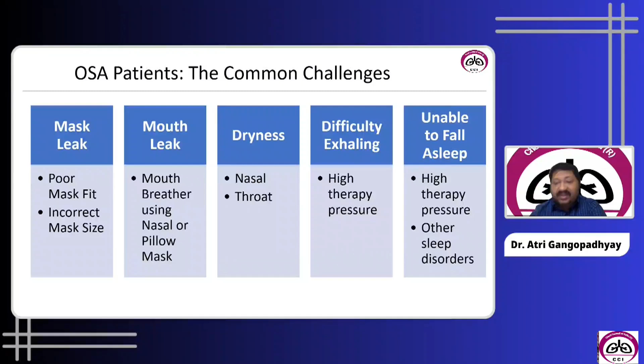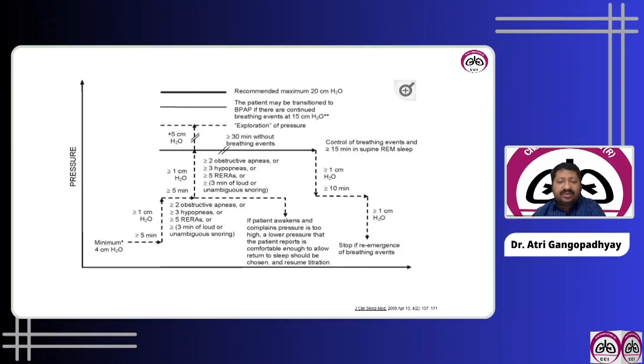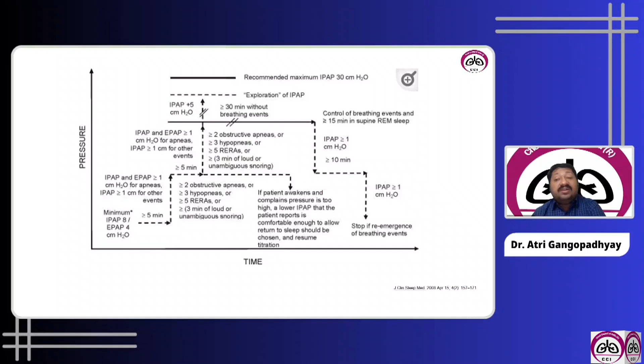So look at these very brief flowcharts. Suppose someone needs a maximum pressure of 20 centimeters of water. Then you can think of transitioning this patient to BiPAP if there are continued breathing events at 15 centimeters. Now, come down by 5 centimeters, and if there is no breathing event for more than 30 minutes, then you can try to decrease the pressure by 1 centimeter, and this way you can go lowest to 4 centimeters of water. Now, suppose you need a pressure of 30 centimeters, then the inspiratory positive pressure may be increased further. You come down slowly by 5 centimeters. If you get better, then you come down slowly by 1 centimeter. So minimum IPAP 8, EPAP 4. So this is how the various algorithms work for tapering the continuous PAP or the bilevel PAP.